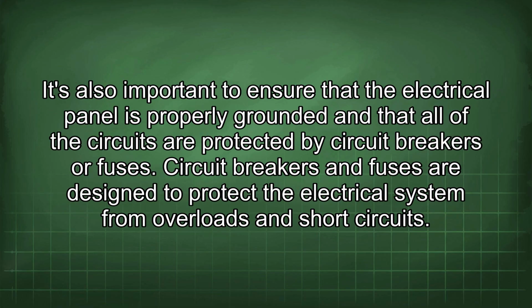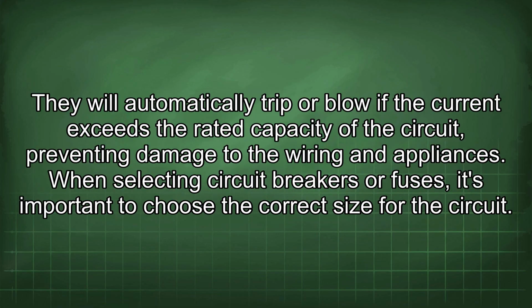It's also important to ensure that the electrical panel is properly grounded and that all of the circuits are protected by circuit breakers or fuses. Circuit breakers and fuses are designed to protect the electrical system from overloads and short circuits.